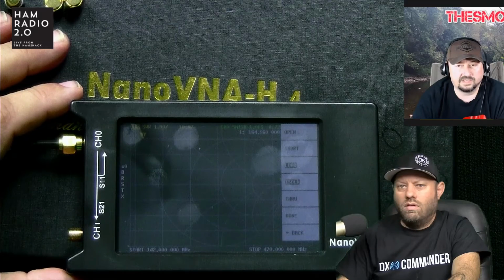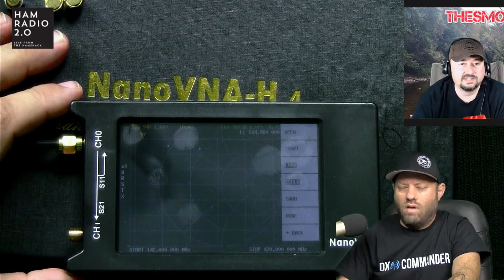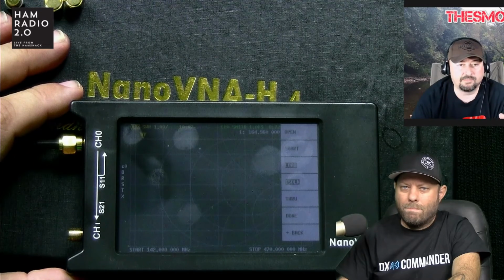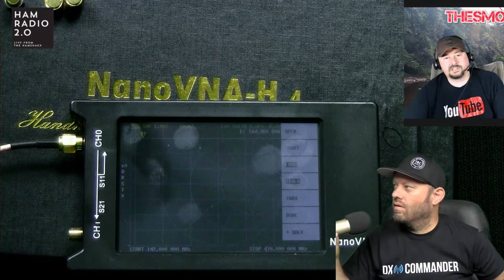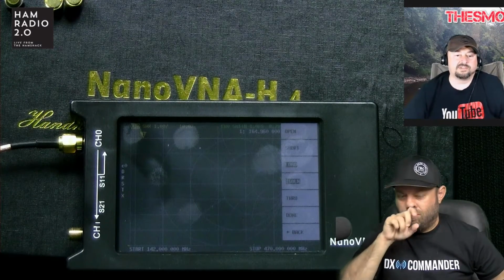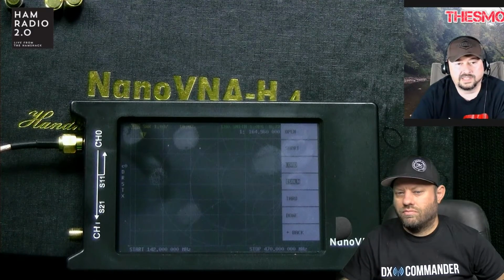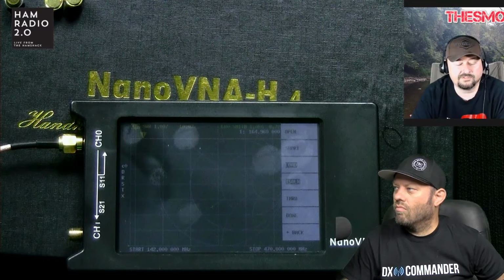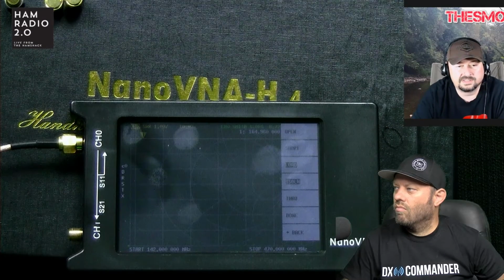Oh, okay. And when you turn the device back on, it goes back to its factory setting. So say you do a calibration for that antenna, and then you want to save it and go mount it out back, you can just turn it on, go into recall, and recall that memory. That way you don't have to recalibrate it all the time. A lot of people think that you have to calibrate it at every usage, but if you save it for that set of frequencies, you should be good. So if I'm going to make a SOTA antenna or a POTA antenna, I can calibrate it, run the sweep at home, and then when I go out in the field, I just plug it in, recall the calibration, and it's much quicker. Right. Well, that makes sense.